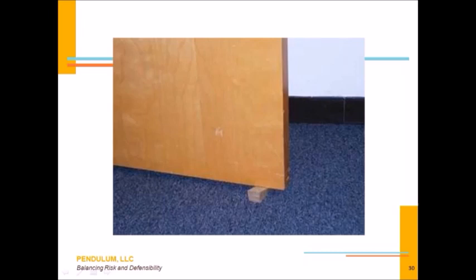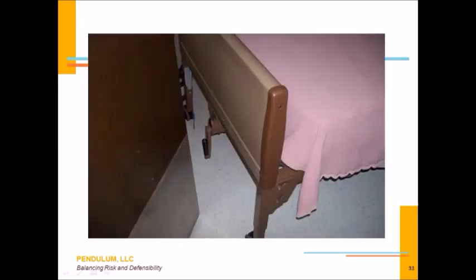The door wedges or the doors that are improperly held open, they've got to go. You're only allowed to open or prop open a door when you do it with an automatic closure or if you do it in a compliant manner with a single action, a push or a pull. And the code outlines some ways to compliantly keep a door held open.